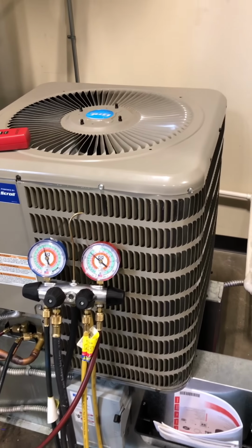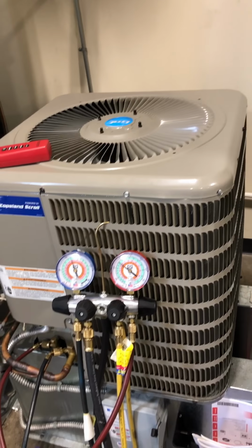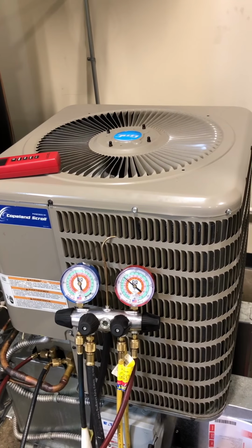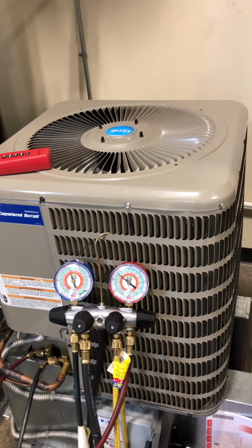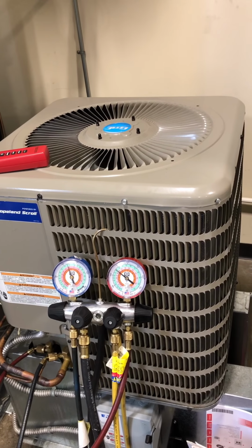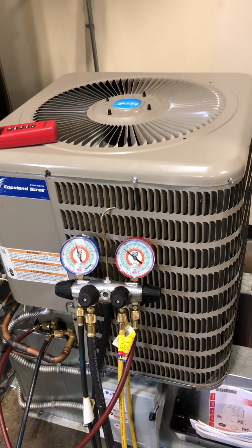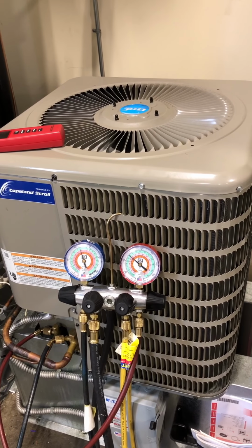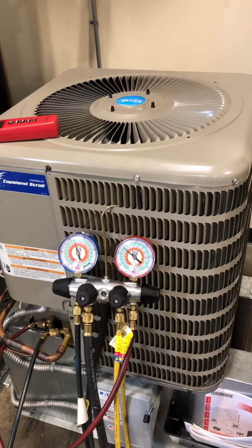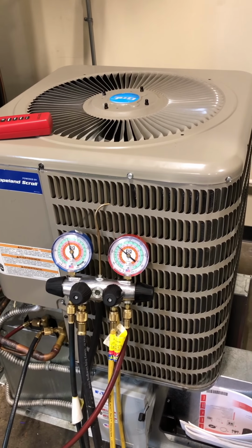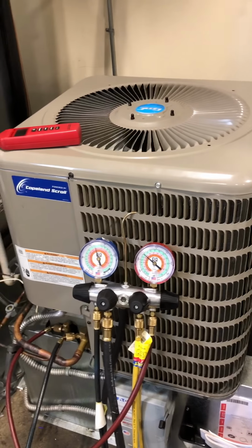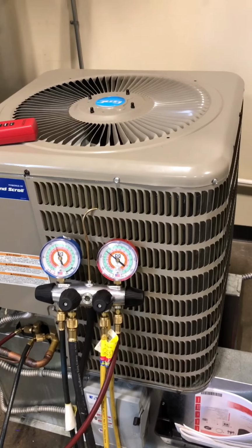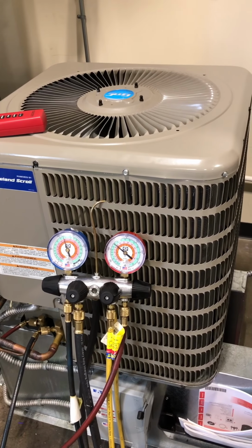Now, a lot of guys will say 30 degrees, and that's true, but it really depends on the age of the system, what SEER rating the system is. The more efficient this system is, the lower that split's going to be. So I like to see it between 15 and 30, depending on how old the system is and what SEER rating it is. If we start getting under 15, we might be undercharged. There might be some other things. If we're over 30, then yeah, there are some problems going that direction as well. I want to see that condensing split between 15 and 30.